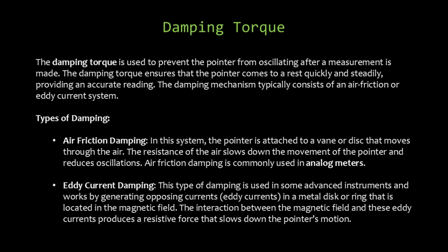Damping torque is the instrument's way of achieving smooth, precise measurements. Its primary function is to prevent pointer oscillations after measurement, ensuring quick and steady readings. Two primary damping methods exist: air friction damping, where a vane or disc moves through air resistance, and eddy current damping, which uses opposing currents in a metal disc to create a resistive force. Think of damping torque as a shock absorber for measurement instruments, quickly bringing the pointer to rest and providing clear, stable readings without unnecessary vibrations.